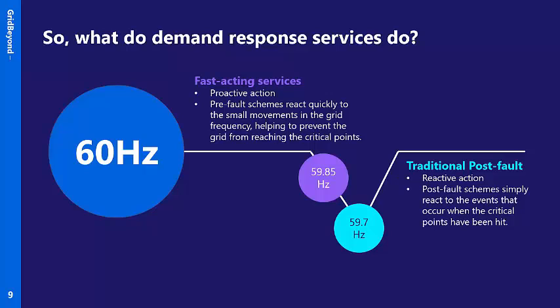So generally on all systems, if there's more than a 0.3 hertz deviation from that 60 hertz equilibrium, then it's a big warning sign that things are about to happen. If that dropped to 0.5 hertz, for example, then parts of the network would see power go off, and they'd see blackouts, potential brownouts, and there'd be issues on the network. So those traditional post-fault schemes are reactive to a changing frequency on the system, a defined point in frequency deviation, and that can trigger some kind of response. Generally automatic, but it's designed to reverse the fault and bring frequency back towards that 60 hertz.